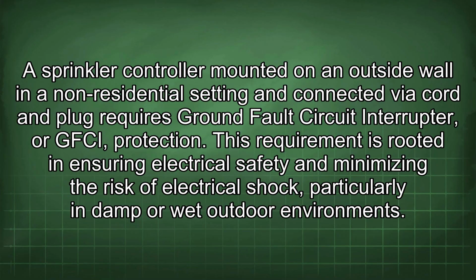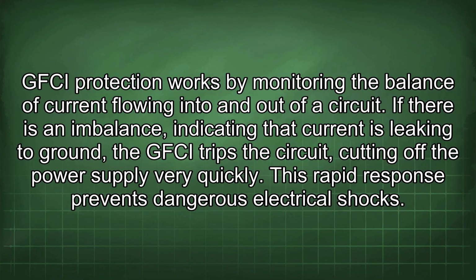A sprinkler controller mounted on an outside wall in a non-residential setting and connected via cord and plug requires ground fault circuit interrupter, or GFCI, protection. This requirement is rooted in ensuring electrical safety and minimizing the risk of electrical shock, particularly in damp or wet outdoor environments. GFCI protection works by monitoring the balance of current flowing into and out of a circuit. If there is an imbalance, indicating that current is leaking to ground, the GFCI trips the circuit, cutting off the power supply very quickly. This rapid response prevents dangerous electrical shocks.